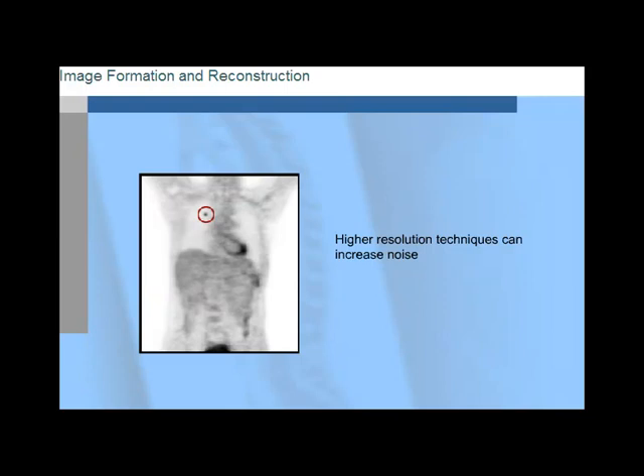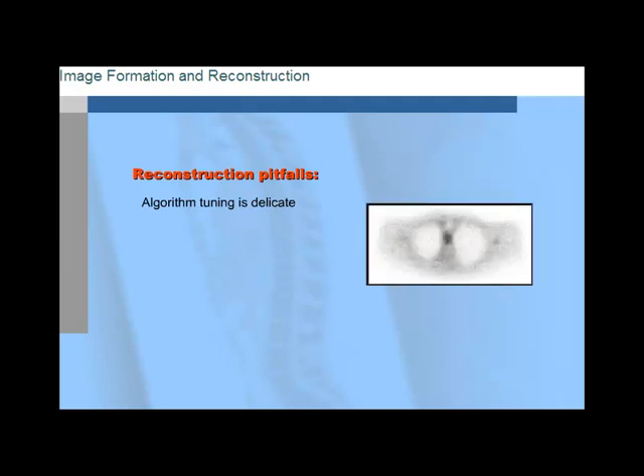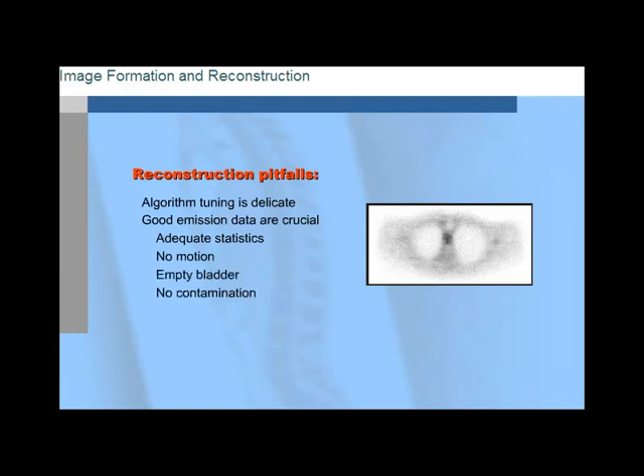Let's examine a few reconstruction pitfalls that you should be aware of. First, algorithm tuning is delicate — every change requires validation on a large data sample, acquired on multiple scanners with multiple detection tasks. Second, no matter how accurate the reconstruction algorithm, no other component can replace good emission data, which can only be obtained with enough statistics, no patient motion, an empty patient bladder, and no patient contamination.